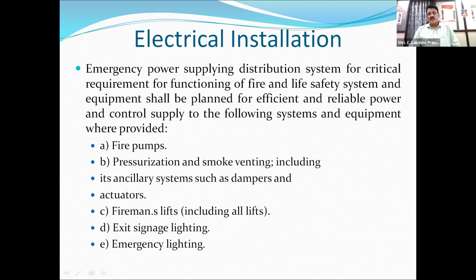Then there should be emergency supply to these electrical installations, especially fire pumps. Then pressurization of the staircases. The present Part 4 of the NBC has made it mandatory that every high-rise building should have a firefighting shaft, which should have a pressurized staircase, a pressurized lift shaft, and a lobby, separated from the building with a 2-hour fire rated door, and the entire enclosure should be 2-hour fire resistant.